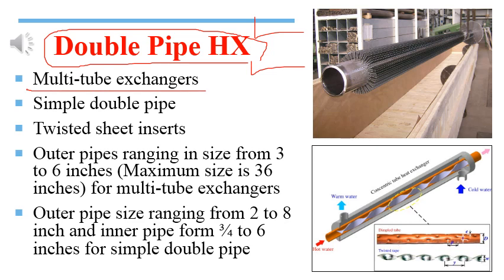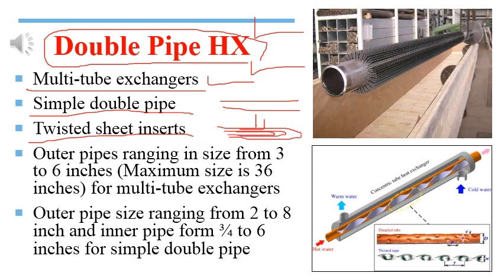The arrangements of double pipe heat exchangers include: simple double pipe, multiple tube double pipe, and twisted sheet inserts. In multiple tubes, the inner pipe is replaced by U-tubes. The simple double pipe uses a single inner pipe. The twisted sheet insert is placed in the inner pipe to cause turbulence in the fluid, which increases heat transfer.